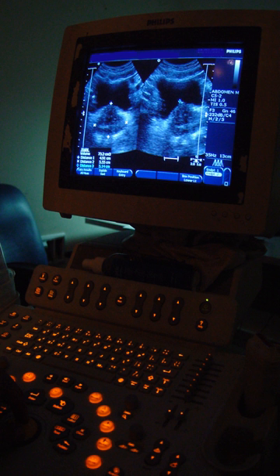and handheld surgical instruments and other similar types of common equipment. Class 2 devices are subject to special controls in addition to the general controls of class 1 devices. Special controls may include special labeling requirements, mandatory performance standards, and postmarket surveillance.